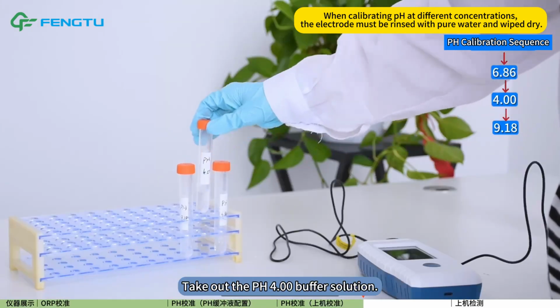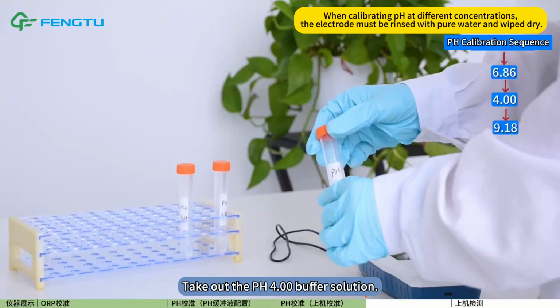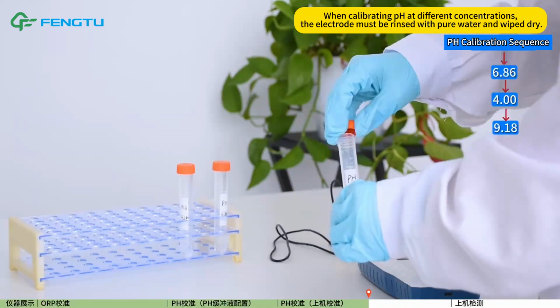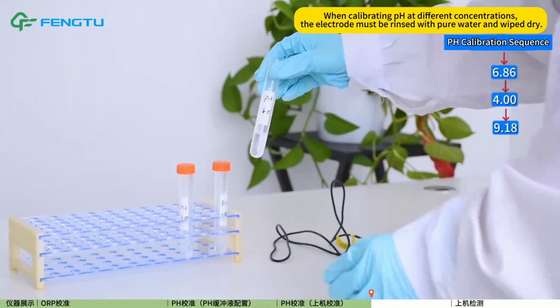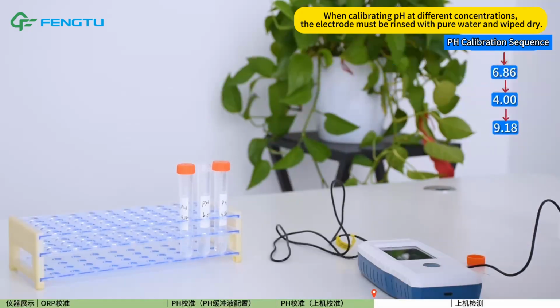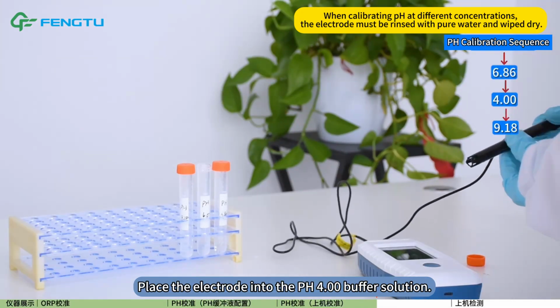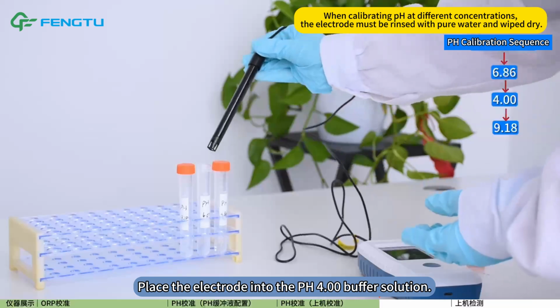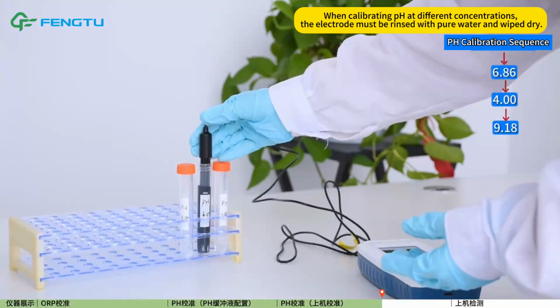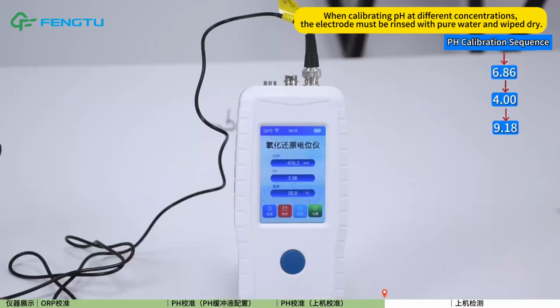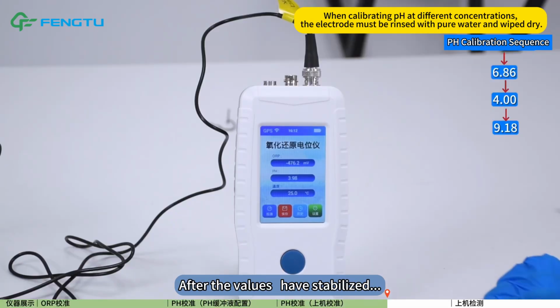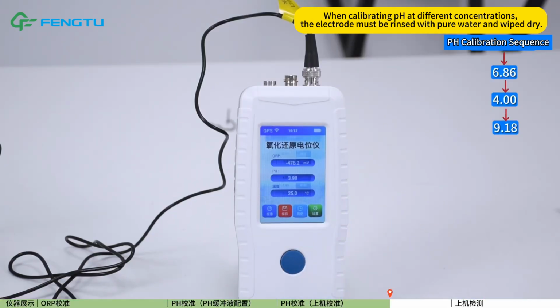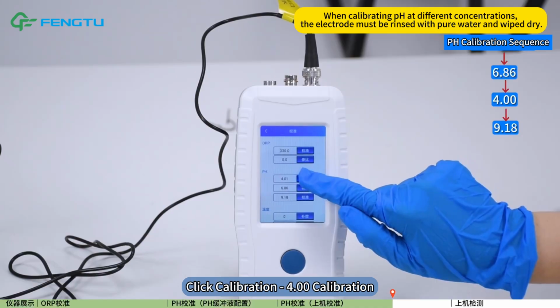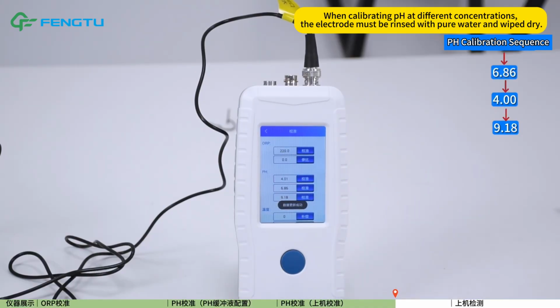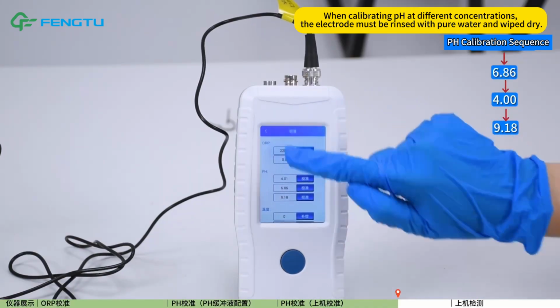Take out the pH 4.0 buffer solution. Place the electrode into the pH 4.0 buffer solution. After the values have stabilized, click Calibration for 4.0 calibration.